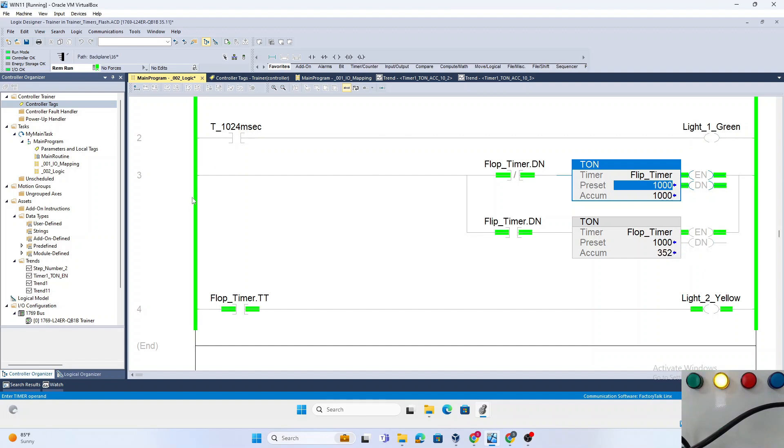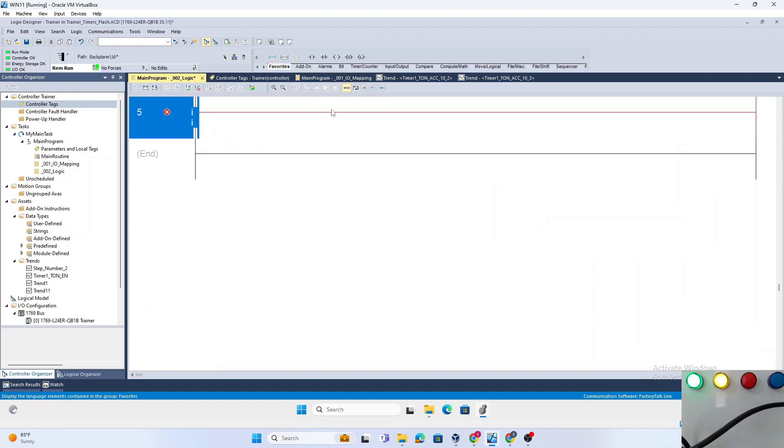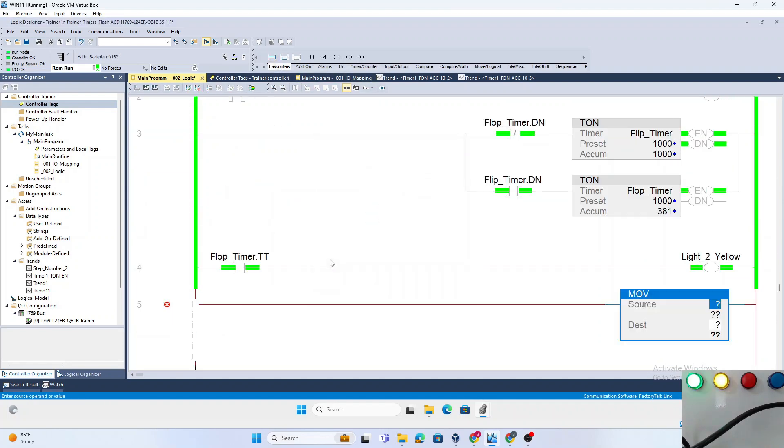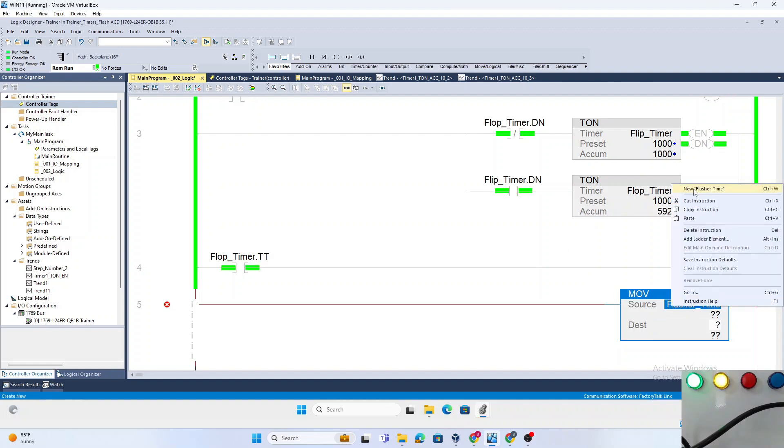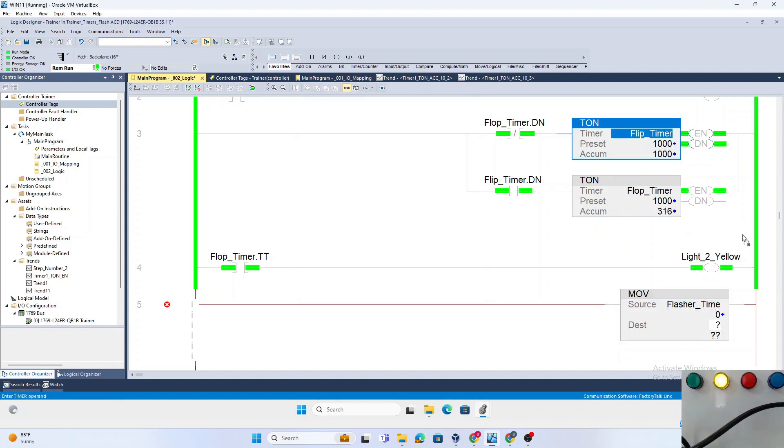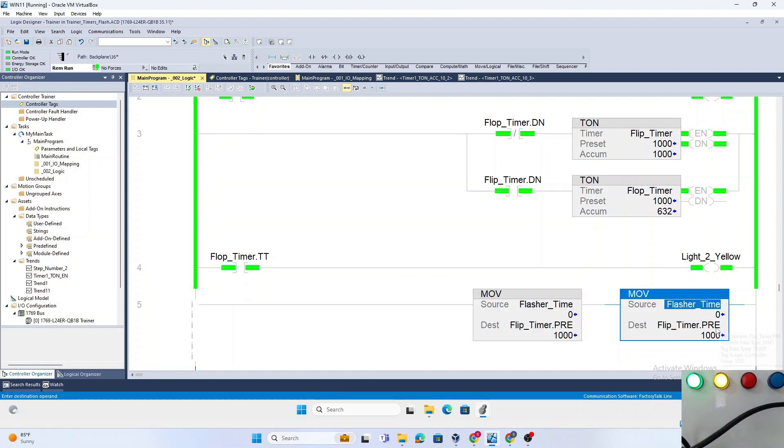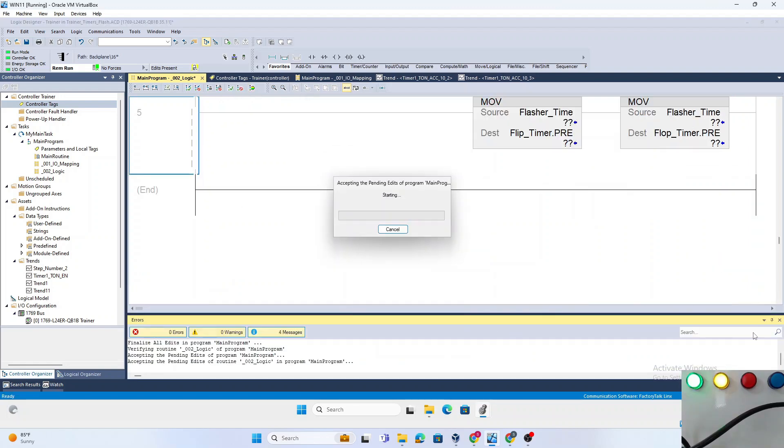We will show that here. If you want to move a preset value, take a move instruction. You could create a variable called Flasher_Time, make it a DINT, and move that into Flip_Timer dot preset. Copy paste that and also move it into Flop_Timer dot preset. Now what we created is a dynamic way to change the timing.